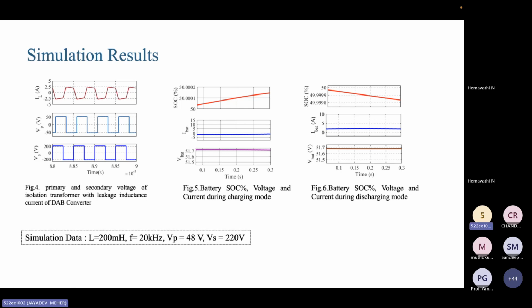When we make the phase difference negative between the primary and secondary, this charging waveform determines the SOC level. The first section of figure 5 shows the SOC percentage increasing from 50% with a charging current of around minus two ampere. I considered discharging battery current as positive, so charging shows as negative. Negative current means battery charging, and the voltage is maintained at 48.